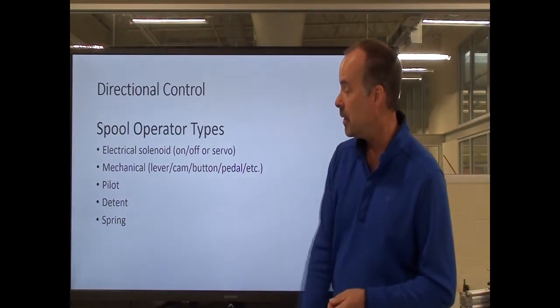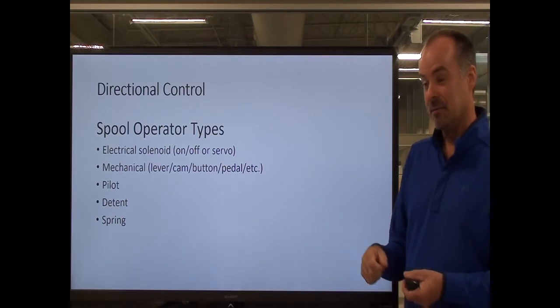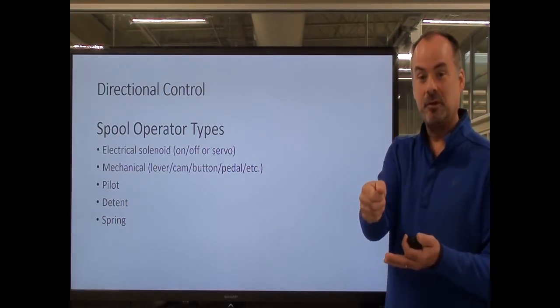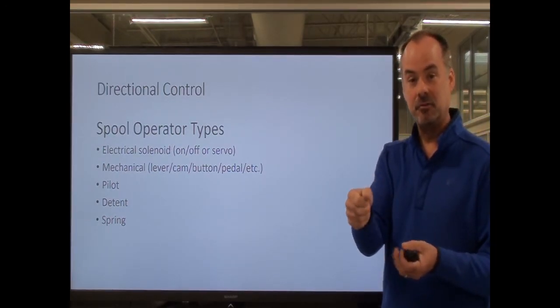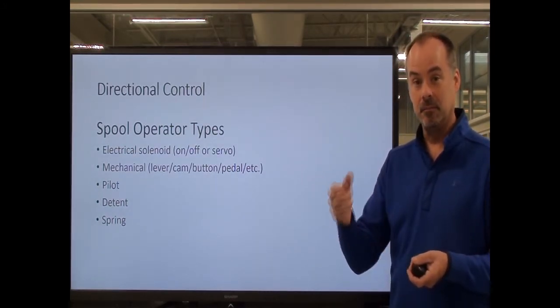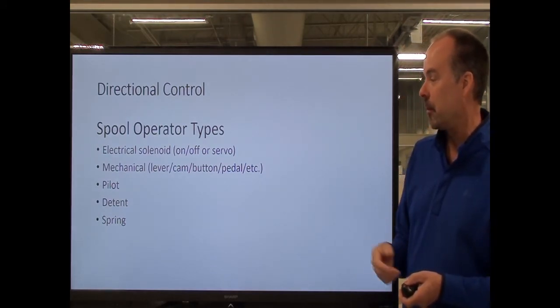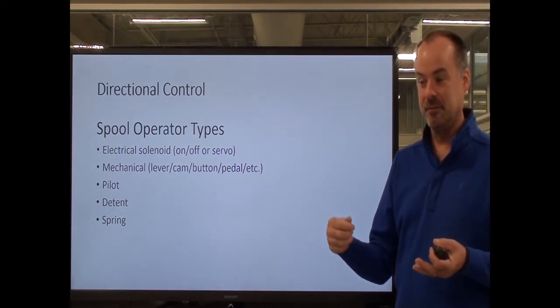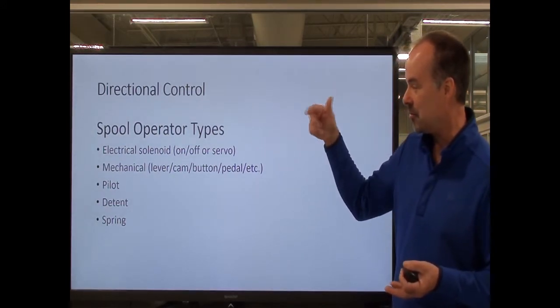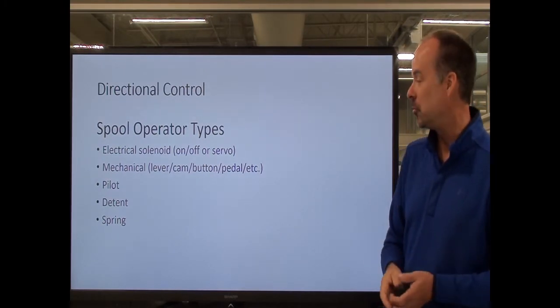You can have a detent-type operator — it's like a gear shift. When you put it in one position, you actually lock or detent into that position. You can let go and it'll stay, and then you have to operate it again to move it out of that position. Spring operators are what we've seen where, when the other operator — whether solenoid, mechanical, pilot, or detent — releases, the spring is used to return the spool to a neutral position.